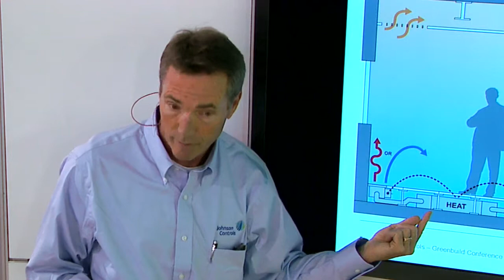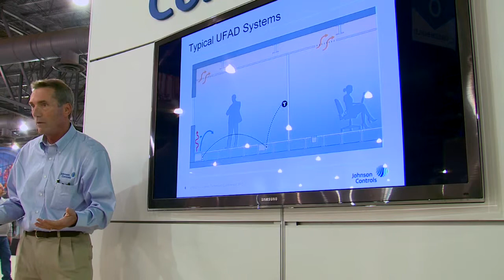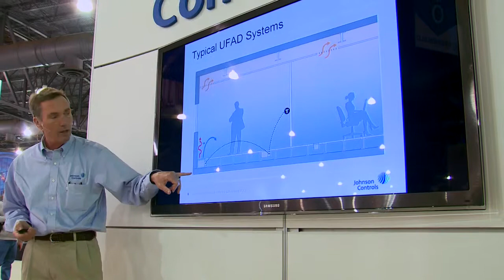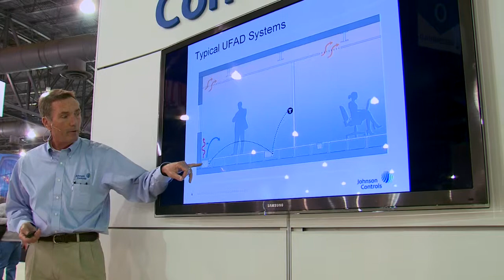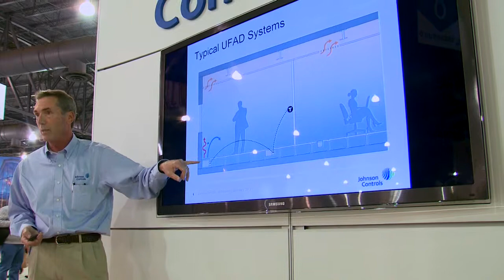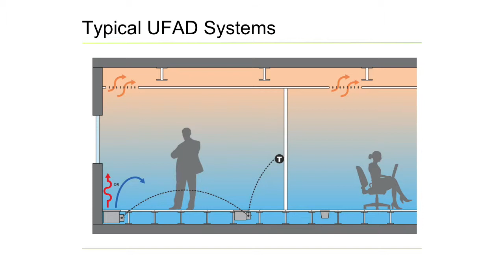And one change that we've seen is this change versus that assisted fan-powered box you saw in the prior slide, which does require some ducting. It's stuff under the floor, if you will. It could be some obstacles, and remembering that our whole design paradigm is maintaining a flexible space. So in this case, what we've seen is a shift away from fan-powered boxes to radiant type products, which you see here, which is essentially a sheet metal box with a radiant element in it. It could be electric or hydronic, and in most cases, even with perimeters with floor-to-ceiling glass, we can handle that cooling load very nicely with radiant products. These could be heating and cooling with or without VAV.